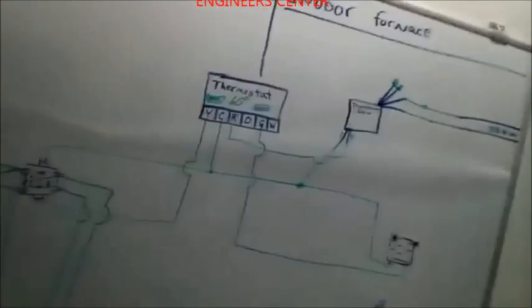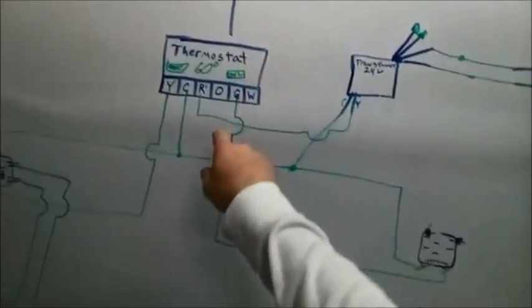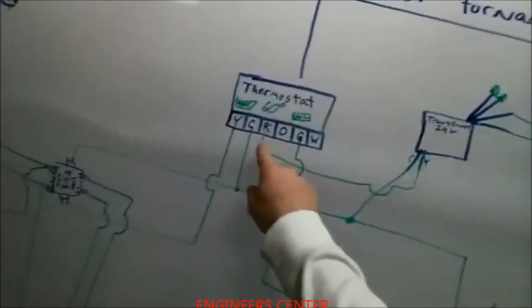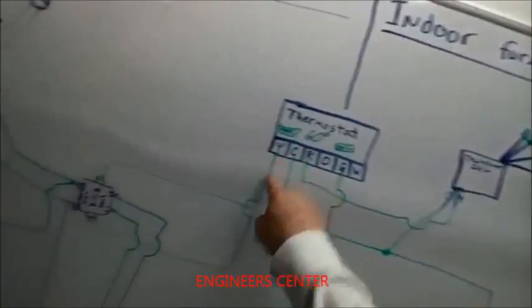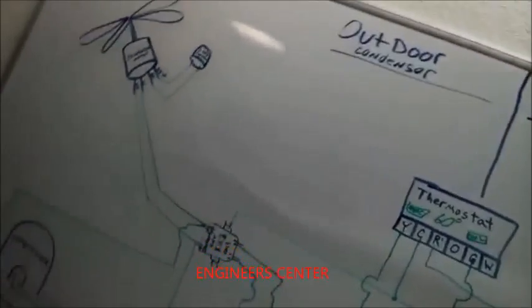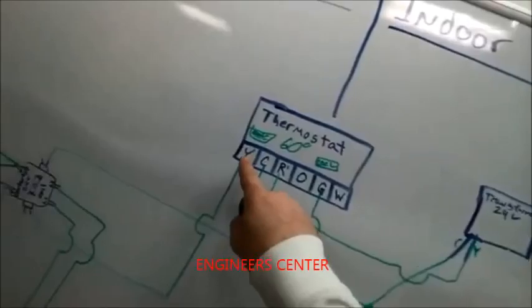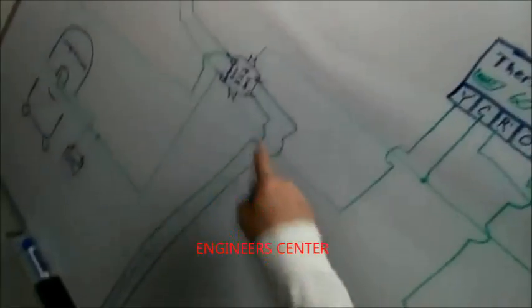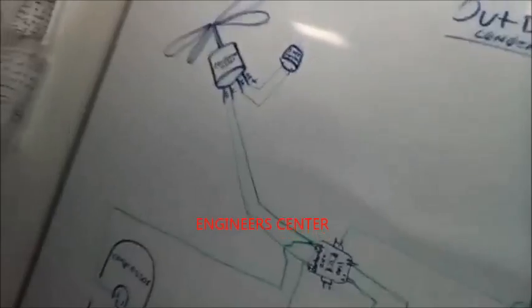So now when the thermostat is turned on in demand, since the coil already has one side of 24 volts straight from the transformer, it'll take the other side of the transformer and send it down yellow to the contactor here, closing it, in fact giving high voltage now to our compressor and our condenser motor, and so our condenser will be on and operating properly as long as it's charged right.